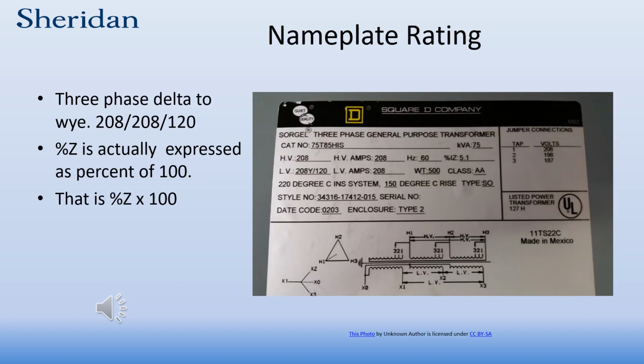Okay, here we have a nameplate of a transformer. It's a three-phase delta to Y, 208 to 208/120. The percent Z, which will be on any nameplate of a transformer, is actually expressed as a percent of 100. So you would take the percent Z we would get from our test, multiply it by 100, and that's what would appear on the nameplate.